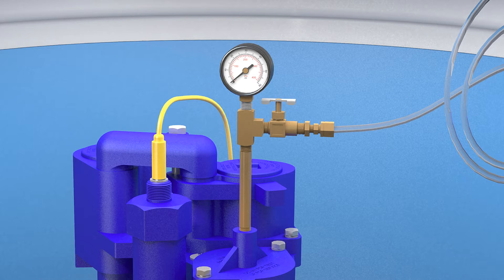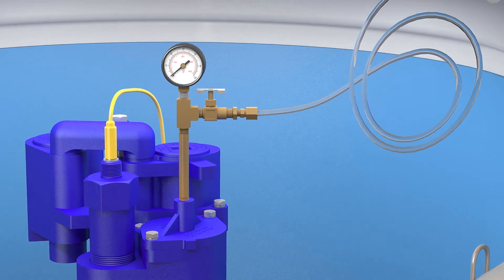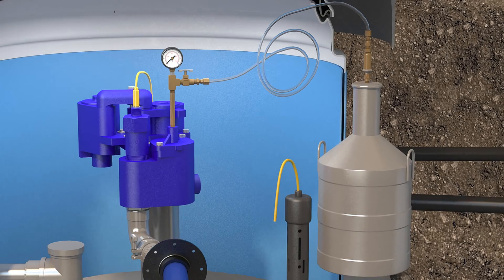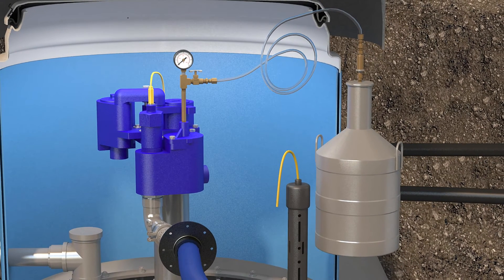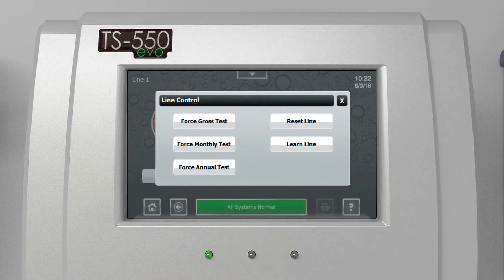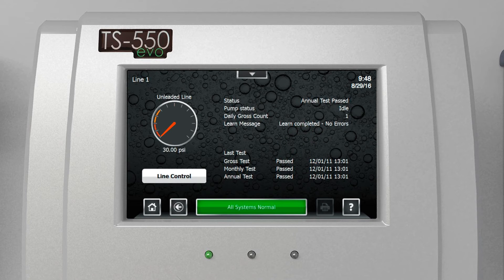The real advantage of auto-learn is that we learn the individual characteristics of each line, which allows us to extrapolate what a leak would look like. There are several advantages to that — primarily, we don't have to enter line characteristics such as diameter and length, which may not be known for every site.